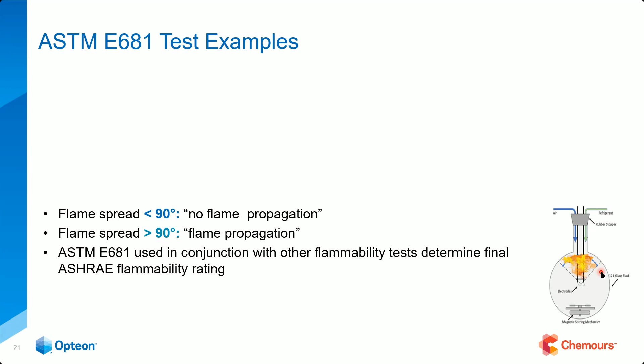When they tested A2L refrigerants, specifically 454B, they saw this—you can see how it just broke the line. I'm not trying to play this down, but the chemists are scratching their heads because they've never seen anything this close to what we're already using. This 90 degree line has a lot of chemistry and formula behind it—there's a reason if it breaks, it has to be classified that way. We've used this standard for years and we can't move the goalpost. So now it's flammable; it's just a matter of how flammable it is.